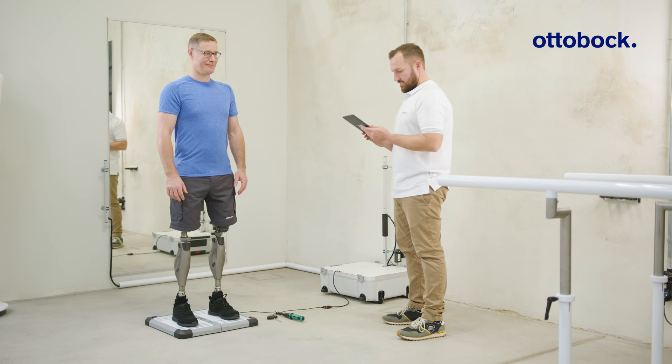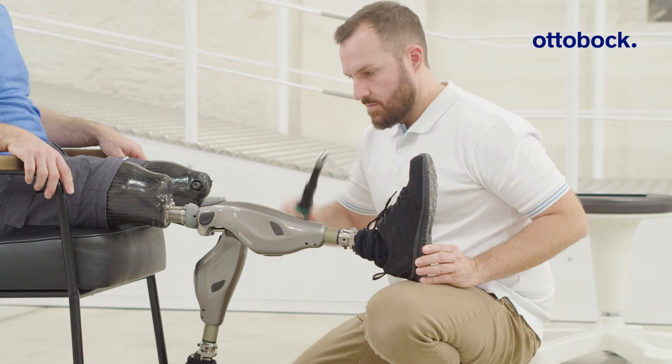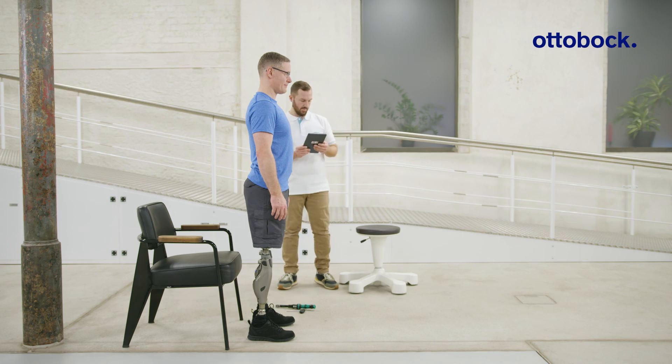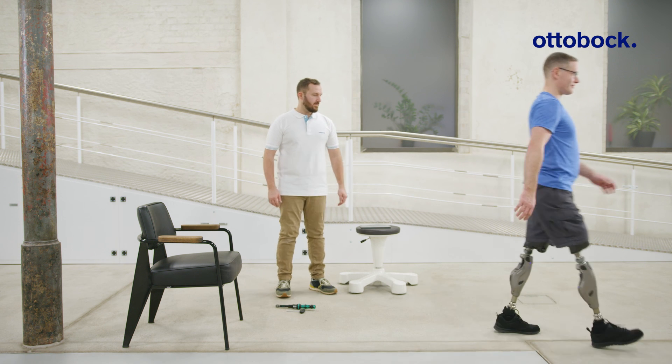Additionally, use the 3D L.A.S.A.R. Posture to check the alignment in the frontal plane. Tighten the screws to 15 Newton meters after each alignment change. Make sure that the knee joint is unlocked after completing the measurement and that there is no collision between the socket and knee joint.